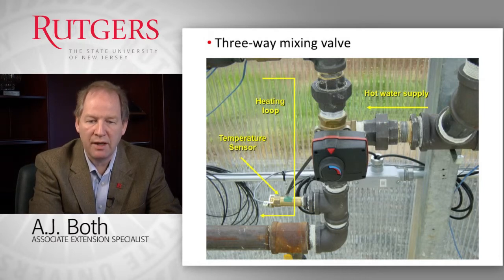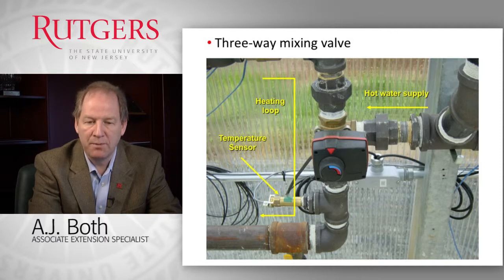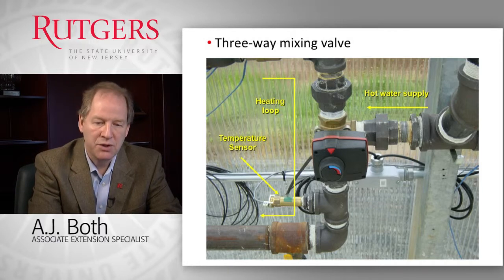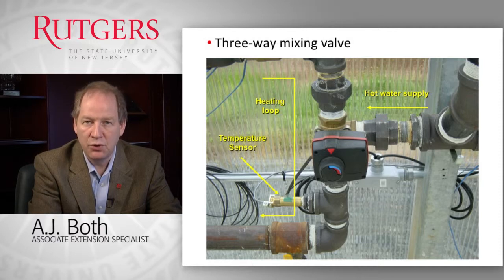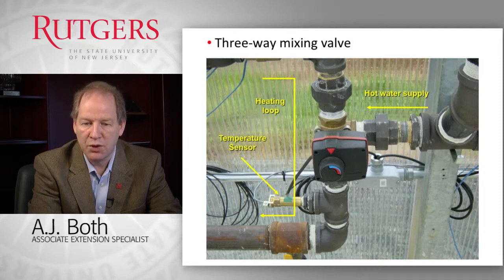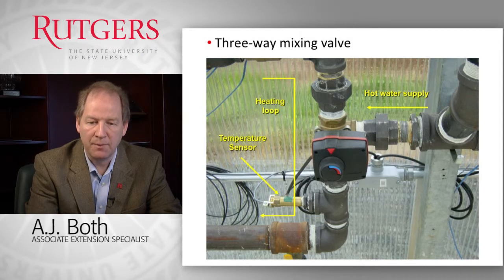Here's a close-up of a three-way mixing valve. Hot water is supplied by the boiler pump on the right-hand side. The three-way mixing valve is connected to a temperature sensor — typically for both water temperature and greenhouse environment. Depending on the control algorithm, the mixing valve opens or closes to allow more or less hot water into the zone to maintain the proper temperature. It's an easy system that allows for pretty precise temperature control.